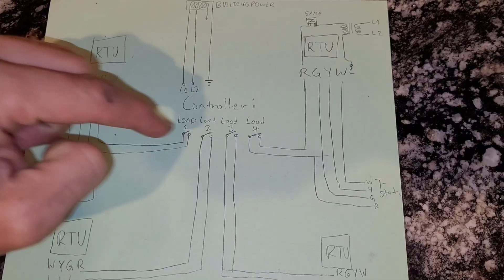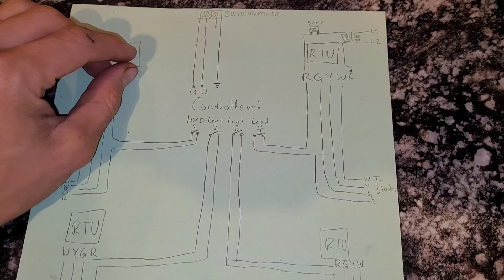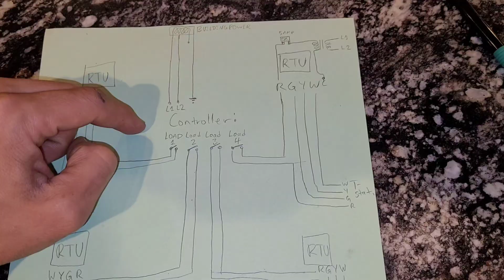First off, the pairs of wires were not correct, and we had 2 additional leads that were not supposed to even be hooked up that were hooked up, so we had an additional 2 more wires, and then they had added that low voltage transformer, I think trying to fix the problem, and then realized that that wasn't really helping, so they had just disconnected it.